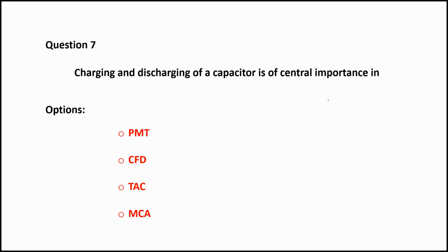The charging and discharging of a capacitor is of central importance in PMT, CFD, TAC, and MCA. A few of these, CFD, TAC, and MCA, are something we had learned earlier in the TCSPC schematics. I'll give a slight detail about each one again.